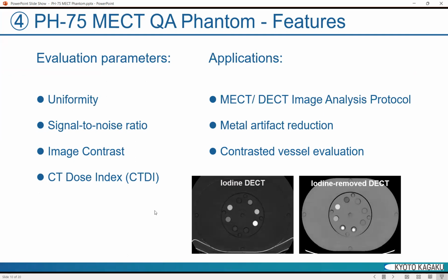The evaluation parameters for our phantoms are uniformity, signal to noise ratio, image contrast, CT dose index. And you can use our phantoms for the applications of multi-energy CT or dual energy CT image analysis protocol, metal artifact reduction, and contrasted vessel evaluation.